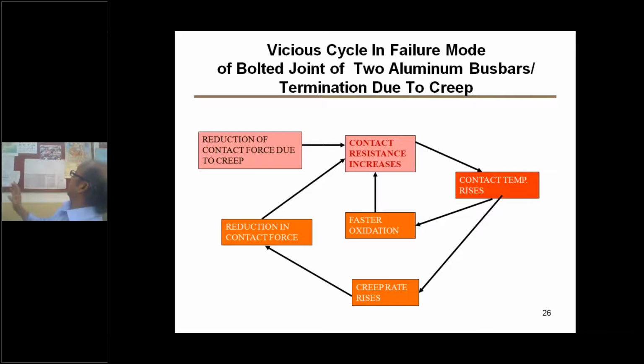Now look at this diagram I made showing how creep behavior changes the life of the contact. Due to creep there is permanent deformation, and the contact force originally applied gets reduced because of the creep, creating play. When there is play, contact resistance increases, and once contact resistance increases, contact temperature rises.